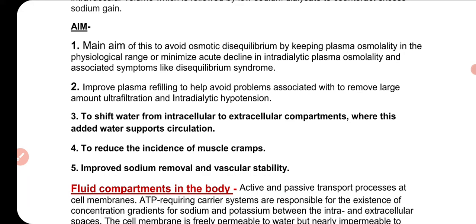We use sodium profiling to prevent disequilibrium syndrome in the patient. Also, plasma refilling is improved, which helps avoid problems associated with removing large amounts of ultrafiltration and intra-dialytic hypotension. Normally we can only remove 800 ml, but with sodium profiling we set the profile in a limited time and limited volume. If we need to remove more water, we can also prevent the patient from hypotension by increasing sodium in the dialysate fluid.